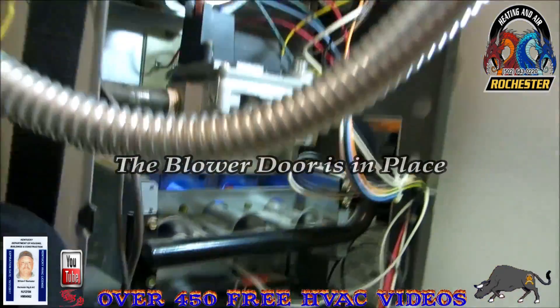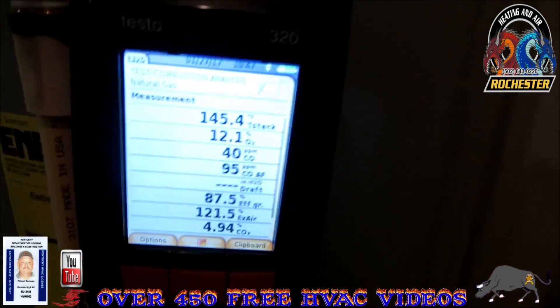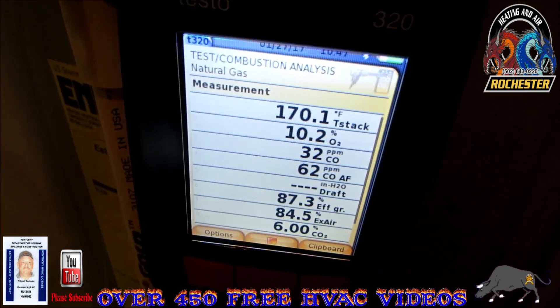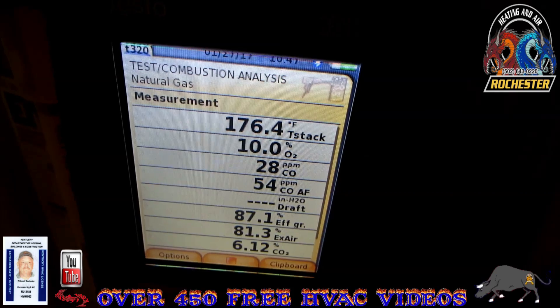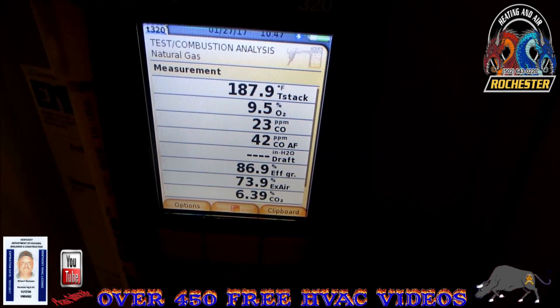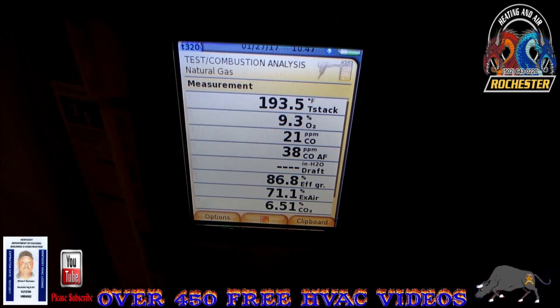It's fired up, we have the gas valve open. Once the blower kicks, we do not want to see the O2 rise. We do have blower — blower initialized at 9.5% O2.